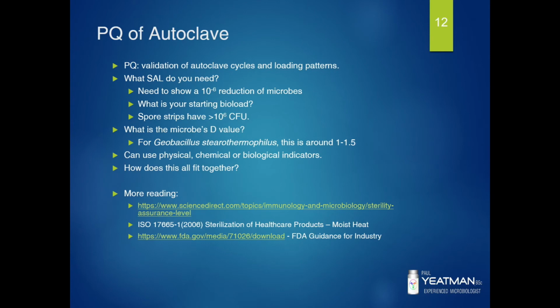So, getting on to the performance qualification, what is that? It's the validation of autoclave cycles and loading patterns. You want to determine things such as what sterility assurance level you need. For example, 10 to 6 is in the FDA guidance, so I encourage you to follow that for sterile products. If it's a medical device which isn't intended to be used on broken or compromised parts of the body, you might use a sterility assurance level of 10 to 3.